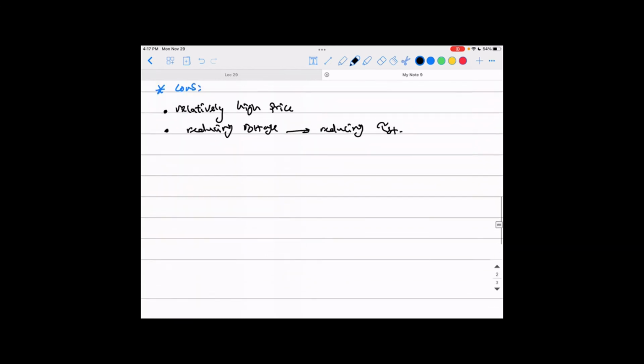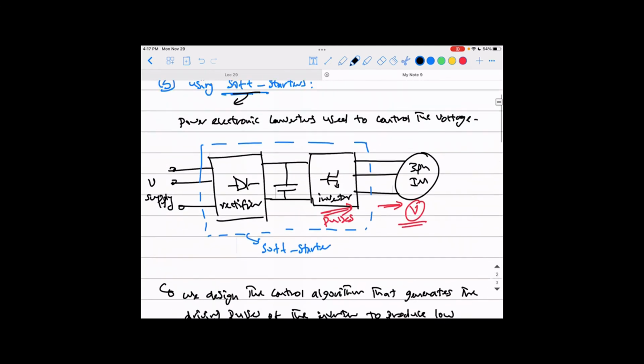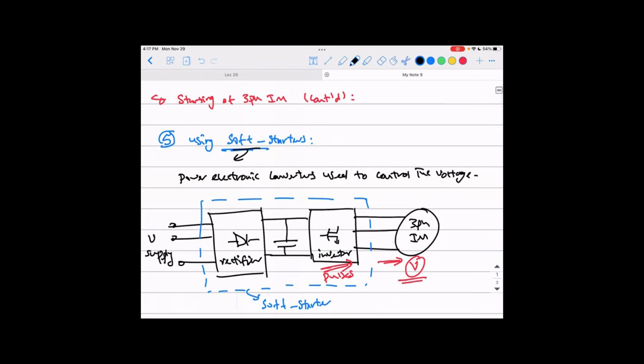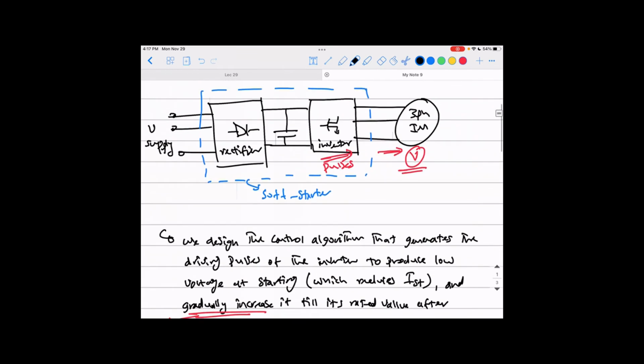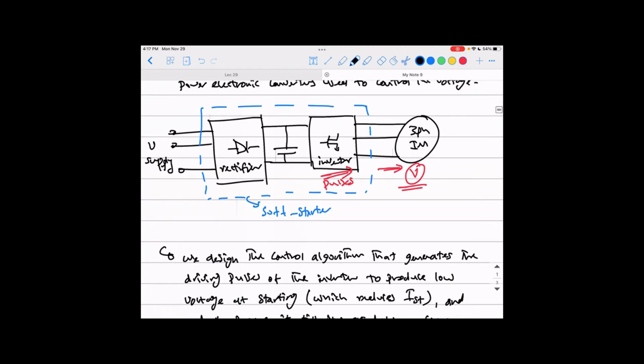Okay. So that's the guy we started talking about here, what we call the soft starter, using power electronic switches to do your job. Again, like I said, it's very convenient if your motor already has a variable speed drive for V over F speed control, so you can use the same circuit for different purposes, which will save you a lot of money. I'm saying, apart from having two different devices, one for control and one for starting, you're using almost the same device to do the two jobs, and that's very good. But if your motor does not have a variable speed drive like that, and you don't need speed control for the motor, then the soft starter would be a very expensive option to go with.